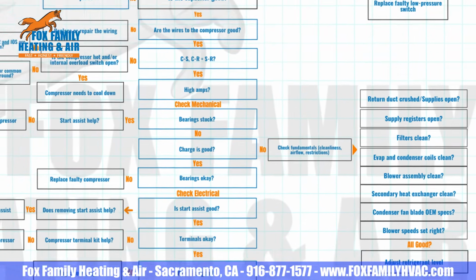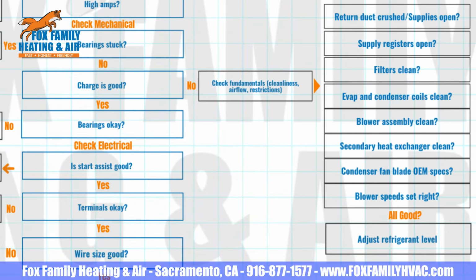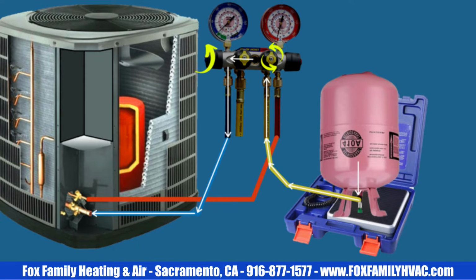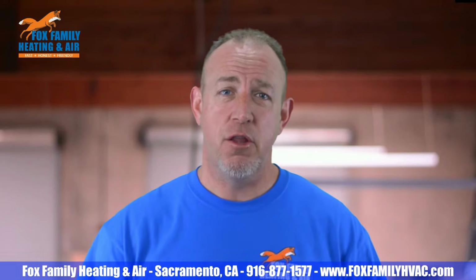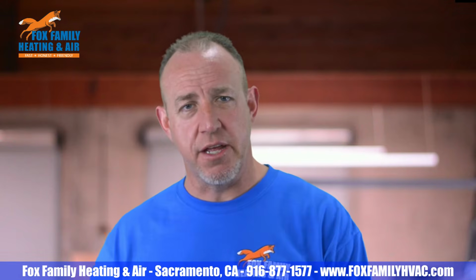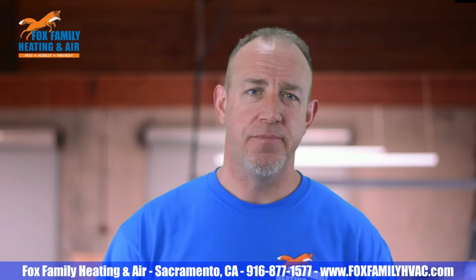So, is the reason that the compressor overheated refrigerant related? I would be ready with your hoses attached to the high and low sides and a tank with a charging scale. That way, when you do fire the system up and you notice low pressures, you don't want to waste time going to get those in case the compressor overheats again. Low refrigerant means low lubricant equals overheating.